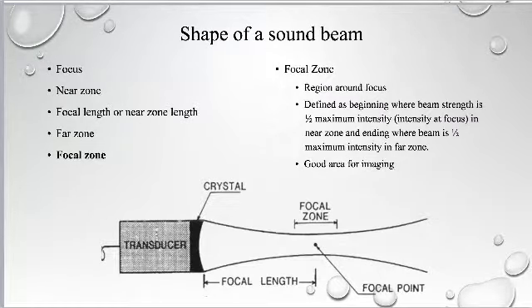Now, we also have an area in our beam called the focal zone. Yep, there it is, focal zone. So the focal zone is this area around the focus that is good for imaging. That's how your book defines it. Area around the focus that's good for imaging. And that's not a bad definition. It works. But there's a better, more precise definition of it that the book doesn't go into, but I will for you.